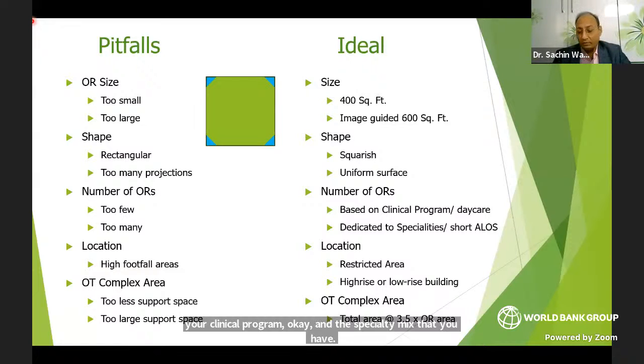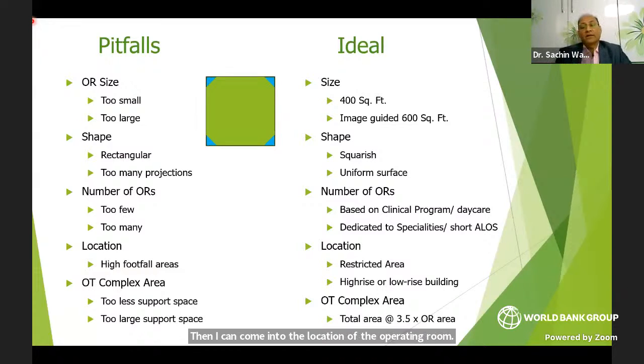Then, coming to the location of the operating room, the obvious thing is that we have to avoid high footfall areas. But again, it depends on the shape of the building, whether it's a high-rise or a low-rise building. It definitely has to be in a restricted area. If you're talking about a high-rise building, then essentially you would have the patient rooms on a tower, say 6th story to 9th or 10th story, and somewhere in the middle you would have the operating rooms, so that you have a service floor in the middle to service the operating rooms. But in low-rise buildings, it is usually the floor below the terrace where you have the operating rooms.